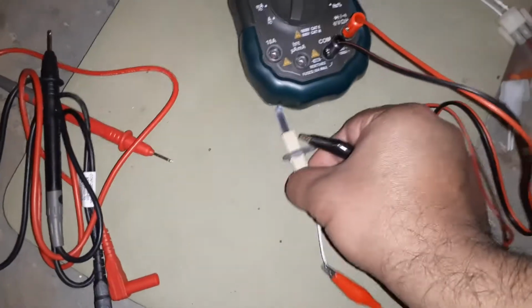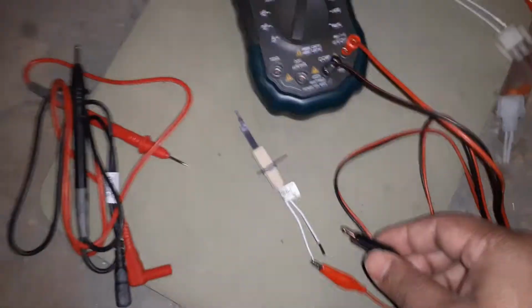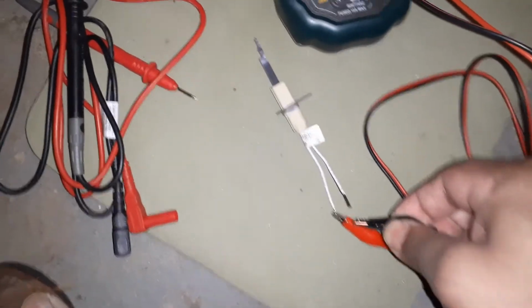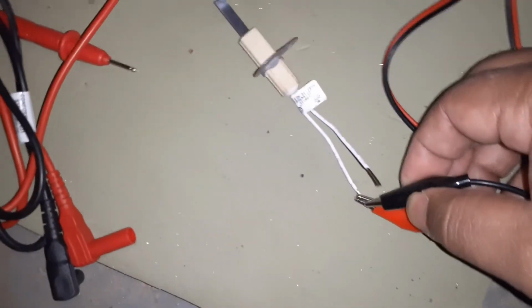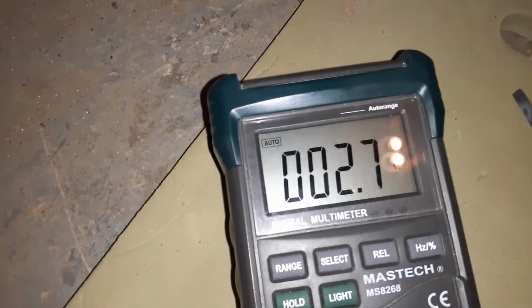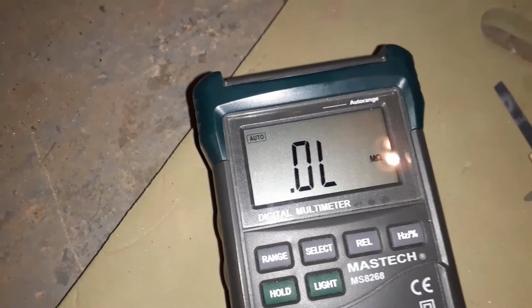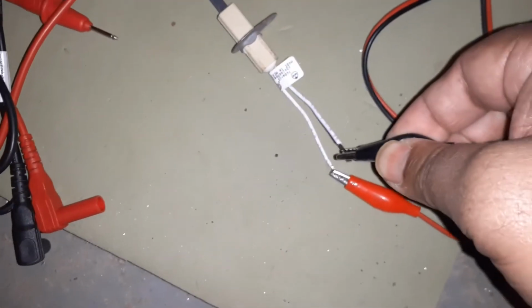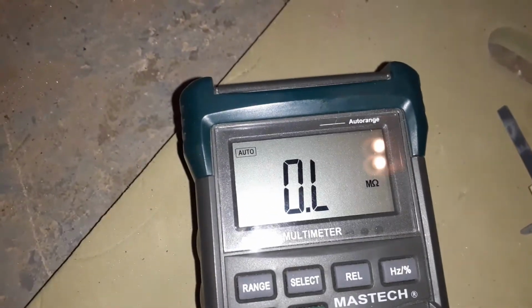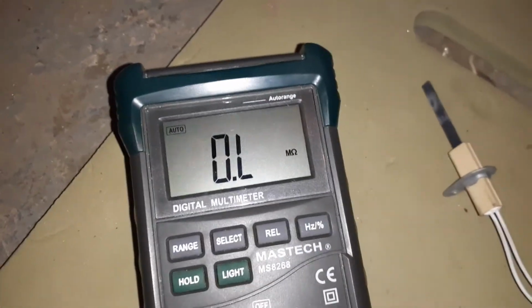What I'm going to do, this was the bad one, and you can see why it is bad. It has broken. But if I check the resistance, first I will check by touching the 2 leads, that's 0 resistance. And then I'm going to connect the lead here, and you can see it shows infinite resistance. 0.L is infinite, which means this igniter is really bad.